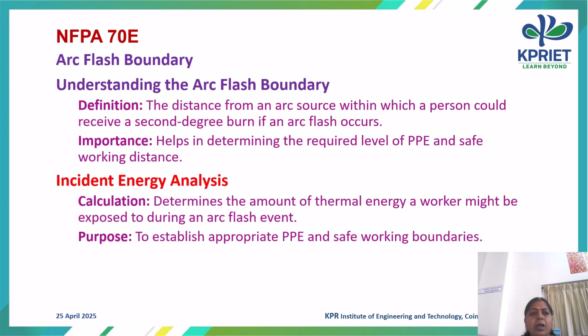This is for the arc flash boundary. Understanding the arc flash boundary means the distance at which a person near the arc source could receive a second-degree burn if an arc flash occurs. This is required to determine the level of PPE and safe working distance.